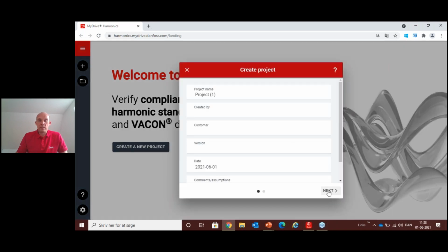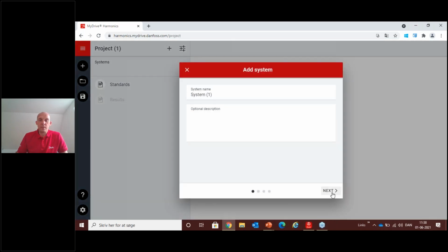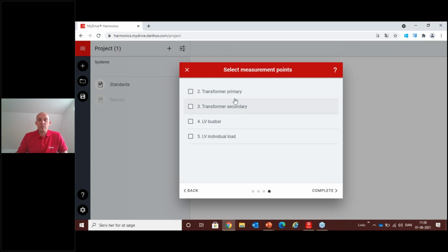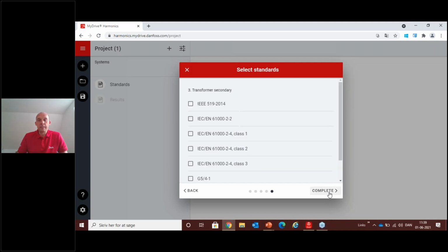So I'll create a project. It'll ask me some questions about my system: which frequency I'm using, the naming of it, and if I want to use calculation on medium voltage or on low voltage. It'll ask me if I'm fed from a transformer or from a generator. It'll ask me where I want to do my analysis, because depending on different standards, there are different ways your analysis needs to be done. I normally take the transformer secondary side when I do calculations. It'll ask you which overall standard you want to comply with, and now I'll just take the IEEE or the EN 61 standard as an example.